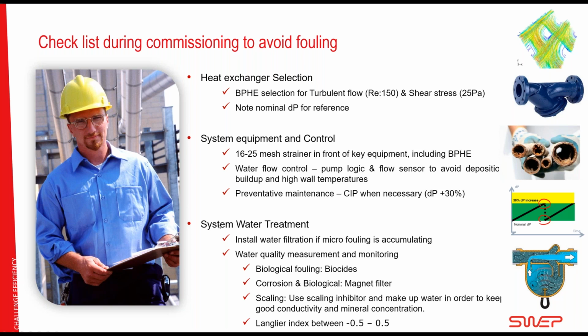And then, water is an incredibly complex matter, and the chemistry of water is immense. If you have a system with microfouling, where a lot of silt is accumulating, you should probably put in some kind of bleed-off filter or cyclone filter to make sure that the concentration of small particles doesn't increase. And use all the recommended water treatments that are out there. SWEP is not a water treatment company. There are a lot of them out there. So if you're working with tough water, get some help.